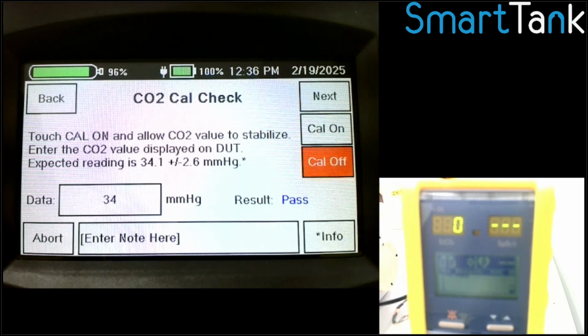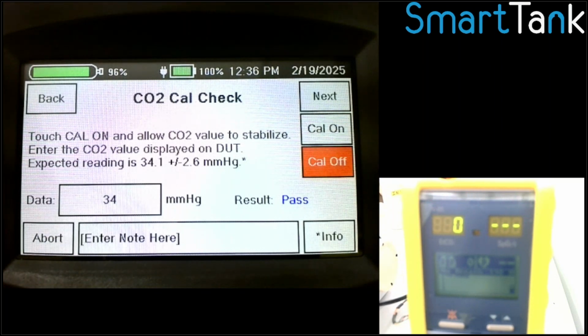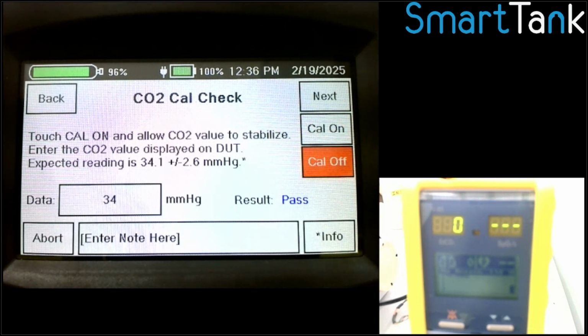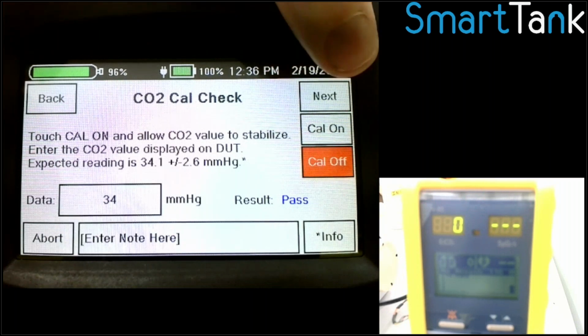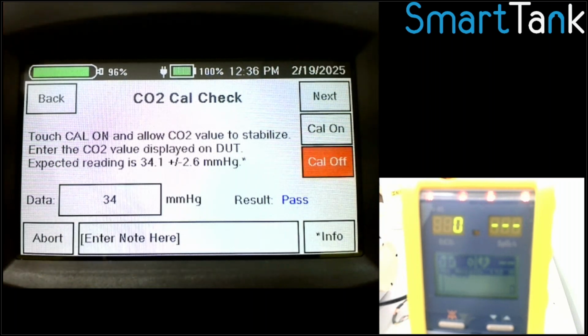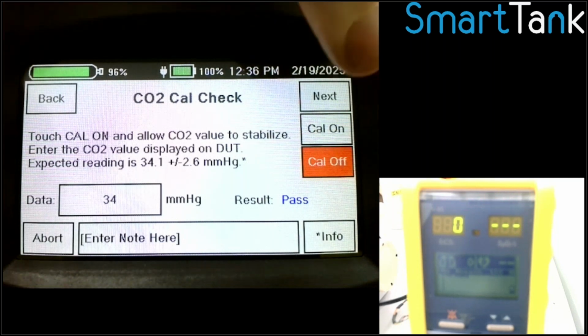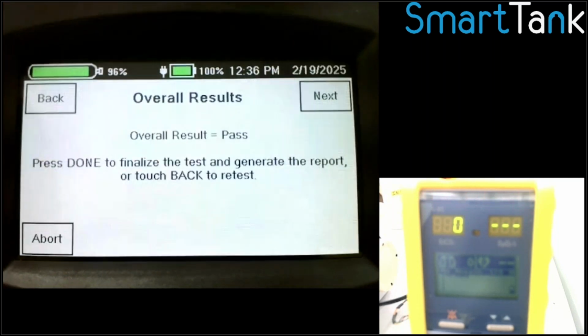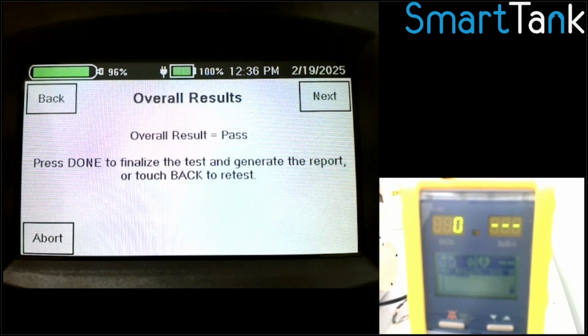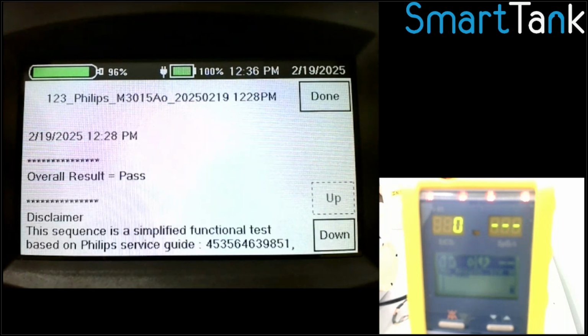I'm done with the cal check. That was fast. Again, I didn't even have to get a regulator. I didn't have to change my tubing. I didn't have that little bag and that menagerie of stuff that you have to get the pressure right. The SmartTank has a manifold built into it and it'll get the pressure down to atmospheric pressure automatically. At this point, I hit next and I'm done. It says I passed everything. It will generate a test report.